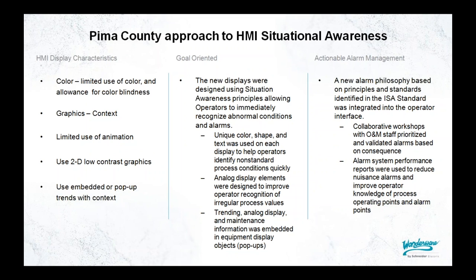So the big thing was color, and we came up with a color scheme through a series of workshops. These were difficult, everyone had their own impression of what go was, what on was, what stop was, what a high-level alarm was. So we pulled all the decision makers into a room for several workshops and came down with a color scheme that was low in contrast. We used different shapes and numbers for those who were colorblind, and very bland, low contrast 2D graphics, so there's nothing to divert the operator's attention away from what he needs to see. We had situational awareness principles like unique color and shape: red is always an alarm, yellow is always a level 2 alarm, things like that.